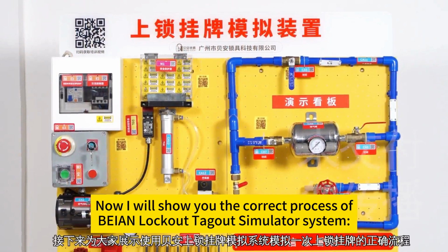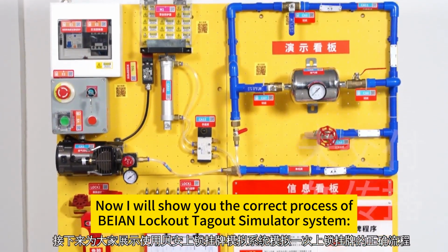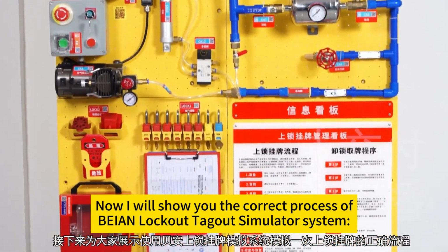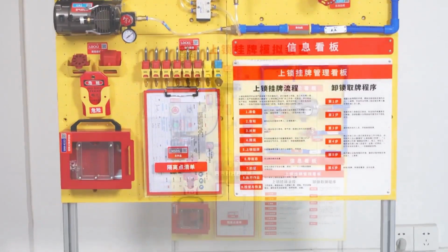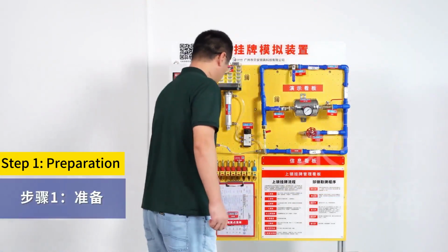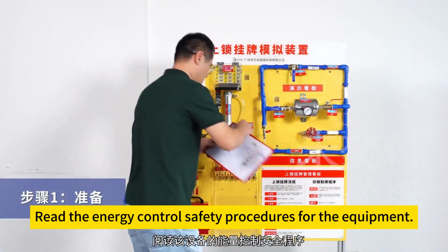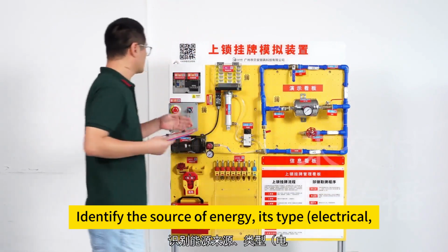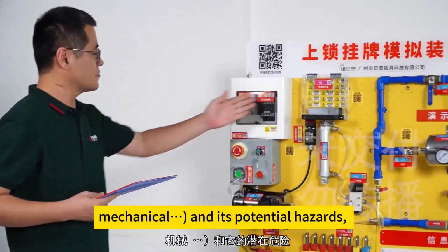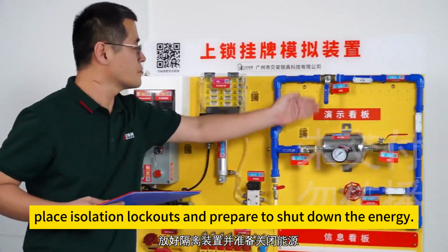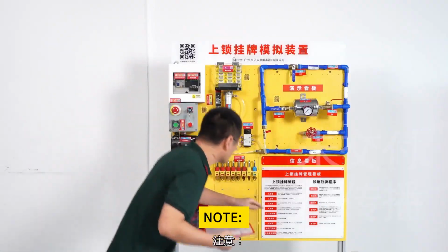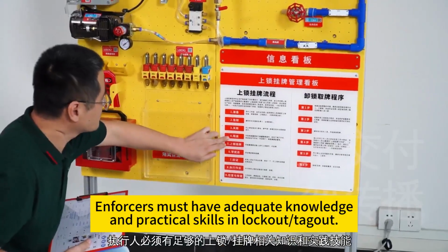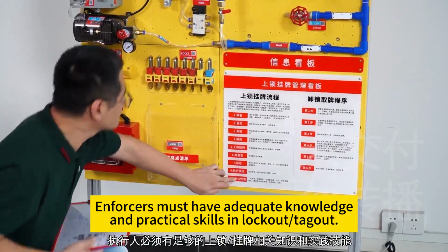Now I will show you the correct process of the Beian lockout tagout simulator system. Step 1. Preparation. Read the energy control safety procedures for the equipment. Identify the source of energy, its type, electrical, mechanical, and its potential hazards. Place isolation lockouts and prepare to shut down the energy. Note: enforcers must have adequate knowledge and practical skills in lockout / tagout.